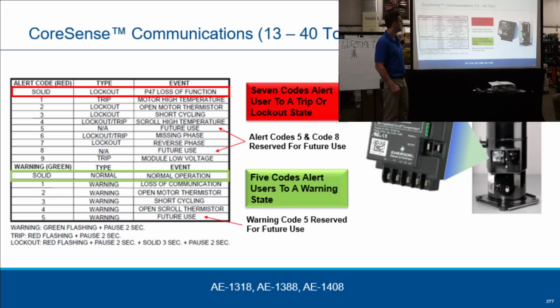Yeah. So this is the air conditioning model. They work the same. They have different trip points. Like this one doesn't have low oil, but same thing. You'll get a flashing light. You read that code and then you look it up. Lock out or trip. Scroll high temperature on 4.